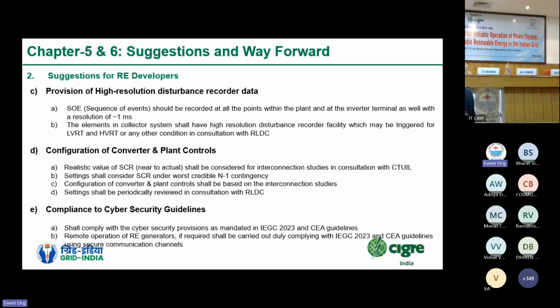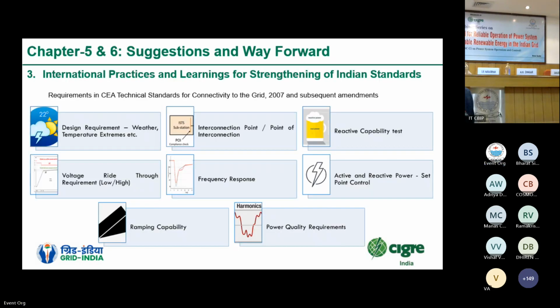The configuration of the converter and plant control should be set as per the operating conditions of the grid at the point where the plant is located, and a realistic value of short circuit ratio, which is near to actual, should be utilized while carrying out the interconnection studies. One suggestion is for cyber security guidelines. Compliance with cyber security guidelines is very important because it is possible that a few plants can be operated remotely, and that can cause really big problems in real-time operation.